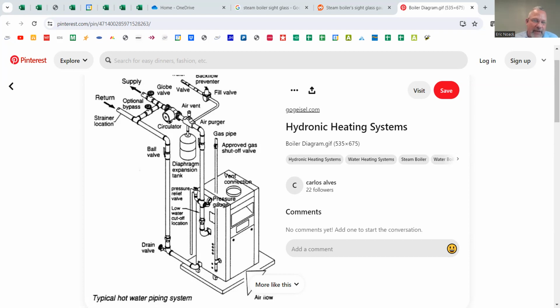So those pressure gauges, you know, they may or may not work. I don't trust them typically as a technician, and in my service bag still, I have a gauge that I can screw on. So there's a boiler drain on these. You can see the drain valve on the backside of that lower piping, and it's got a threaded hose bib on it, just like a hose silcock on your home. But I have that kind of fitting on my pressure gauge and I can screw it on and I've got a gauge that I know I can trust, and then I can check the pressure in the boiler. So that allows me to diagnose and find out why it might be dripping out of the pressure relief valve.